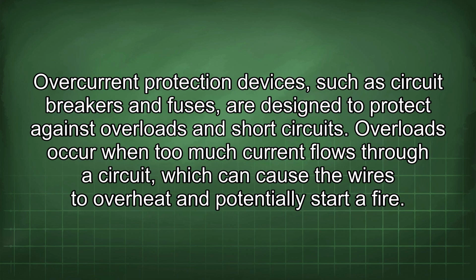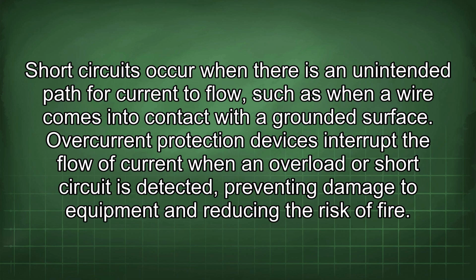Overcurrent protection devices, such as circuit breakers and fuses, are designed to protect against overloads and short circuits. Overloads occur when too much current flows through a circuit, which can cause wires to overheat and potentially start a fire. Short circuits occur when there is an unintended path for current to flow, such as when a wire comes into contact with a grounded surface.